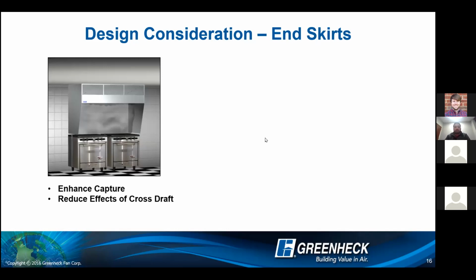So what do we do when we have to mitigate these? You just have a door, you have a high traffic area, and you have to put a diffuser within 10 feet of the hood just based on your ceiling height or your ceiling layout. What I would recommend doing is putting end skirts on these hoods. These end skirts are going to enhance your capture and reduce the effects of cross drafts. If you go back to your image of that door opening right here, and you have the full end skirt on, when the air comes from that door, it's going to be blocked by this end skirt. So it's a very cheap way to mitigate these simple problems in the field, and then you just don't have the problems when they come up.